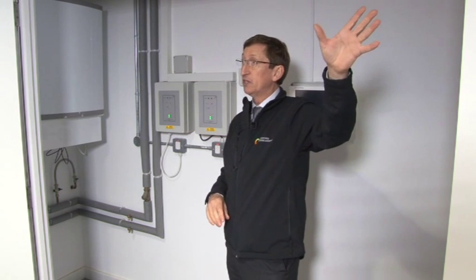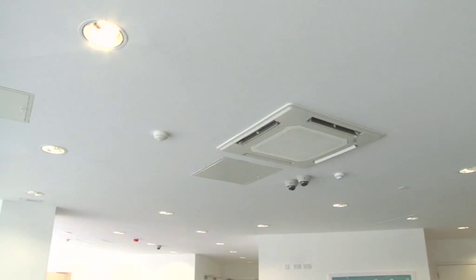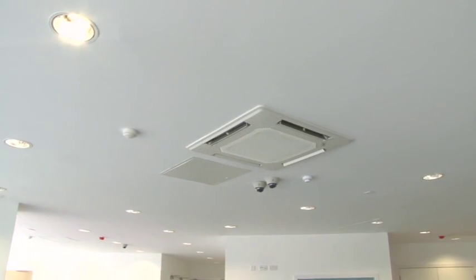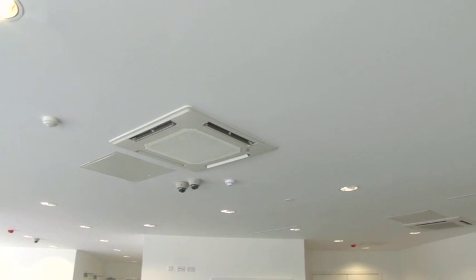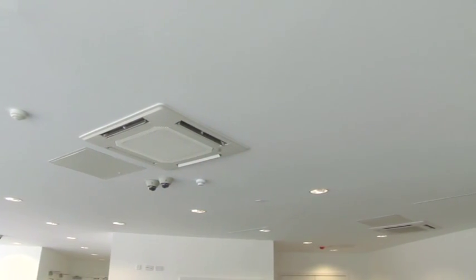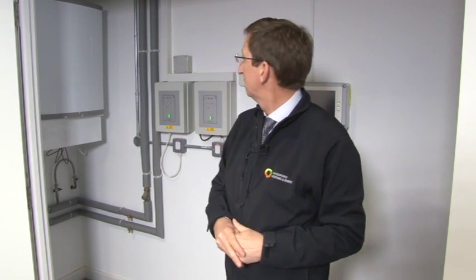Okay. The other part that the HIU provides heat to is some ventilation units which are up in the ceiling, and there's two within the area. One within the main reception area here, and also one round in the gym. So what they're doing is providing the ventilation to the area. They're heat recovery units that are transferring heat between the incoming air and the outgoing air. But they've also got a heating coil on them as well, just to temper that incoming fresh air on a cold day, to make sure we're not feeding cold air into the place.